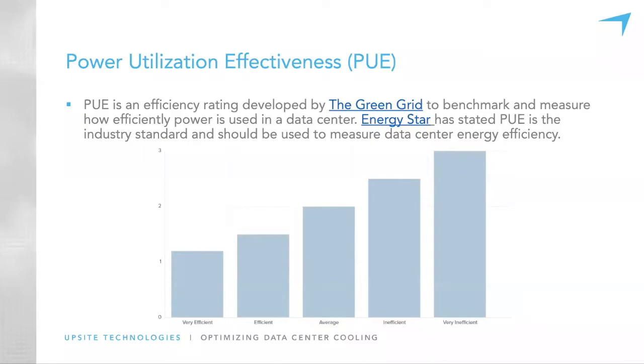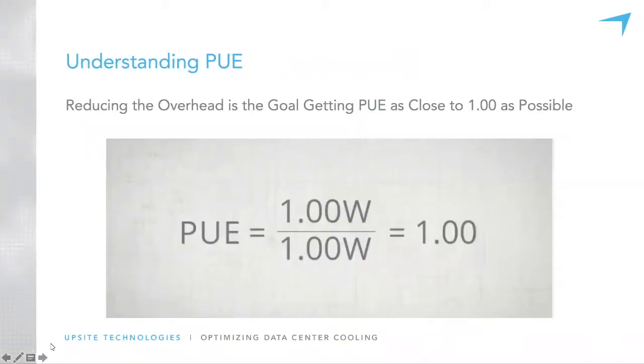And I think a lot of data centers were trying to hang around the 2 for PUE, but certainly the 1.3 to 1.5 seems to be more of the industry standard. So if we go to calculate PUE, having a PUE as close to 1 as possible is the goal. I don't know that is right now with the technology we have completely possible, but the idea says if I have 2 watts of power coming in, 1 watt for facility, 1 watt for IT equipment would be our ratio.